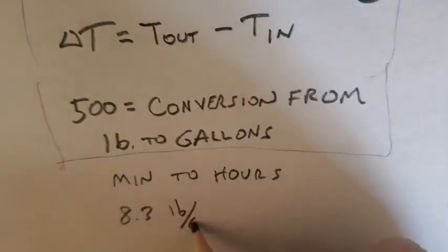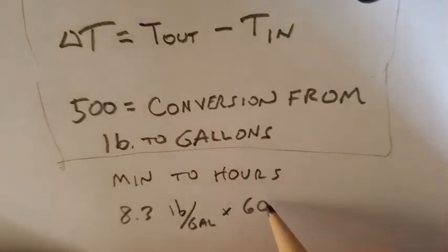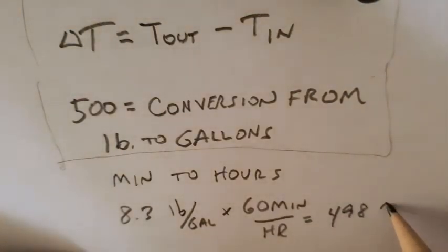A gallon of water weighs about 8.3 pounds. Using 8.3 pounds per gallon times 60 minutes an hour, we come up with 498, which is about 500. And that's why we use 500.